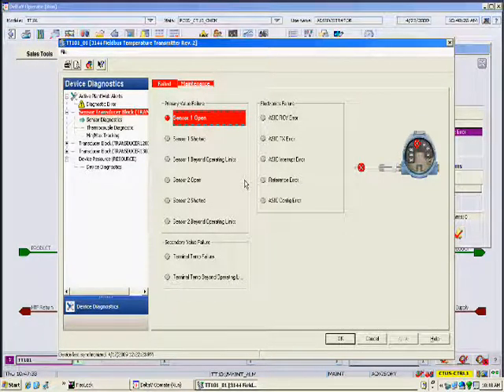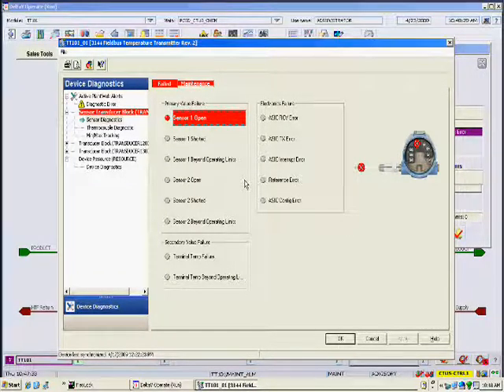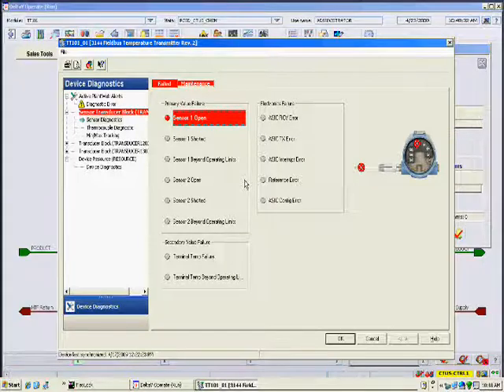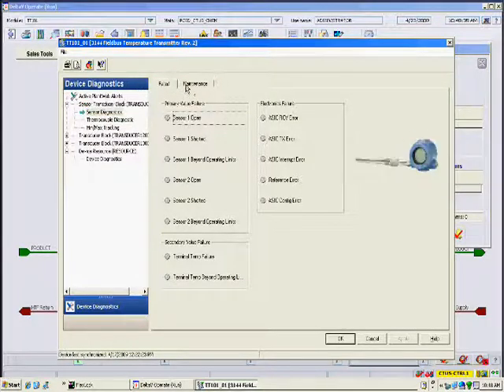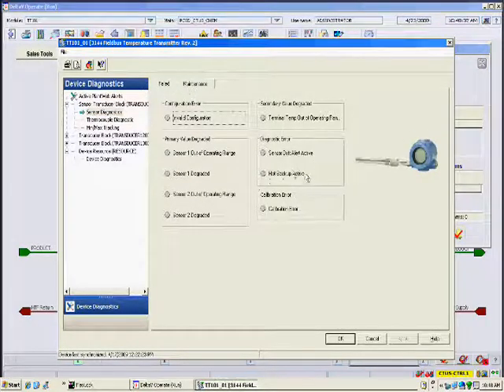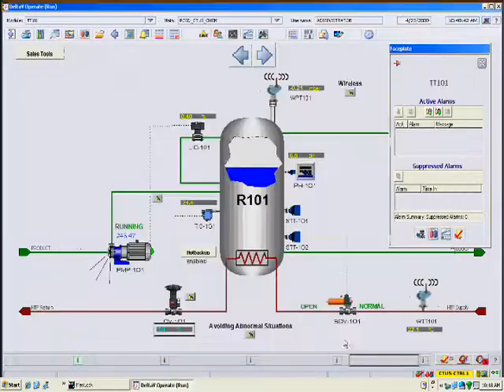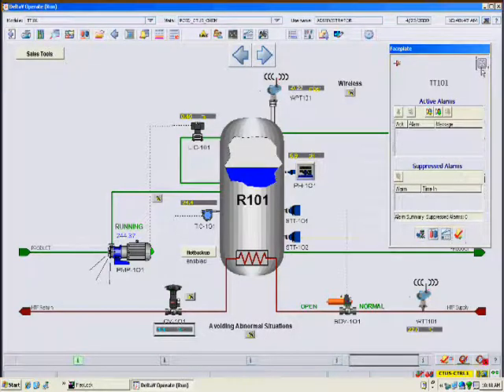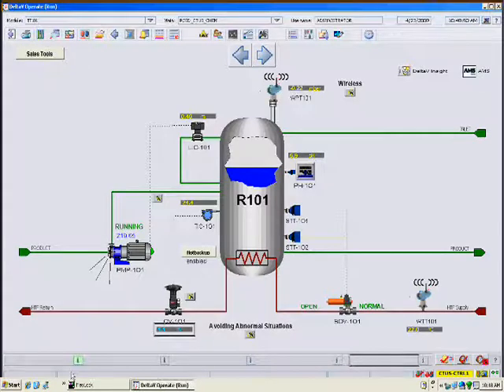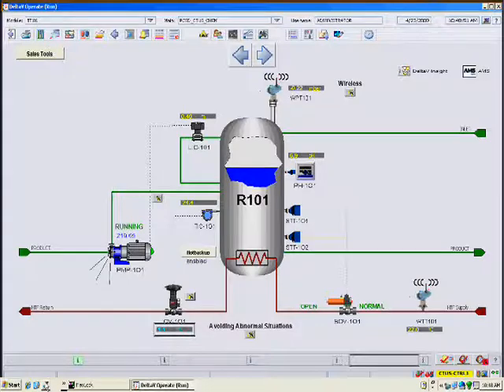Had the operator not received this alert and called on the technician, it is unlikely the technician would get to know about the failed sensor any time soon, since the technician is busy in the field and may not login to the maintenance computer very often. Once the problem is fixed, the diagnostics indicator and conditional image automatically change to show the device is okay. It is up to plant alarm management philosophy whether a non-critical maintenance warning not affecting the process shall be enunciated on operator stations, or if only critical failures affecting the process shall be alerted to operators.